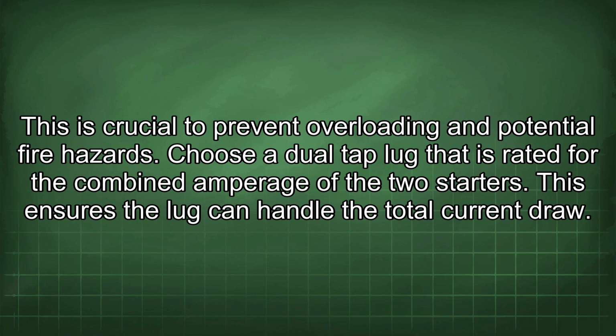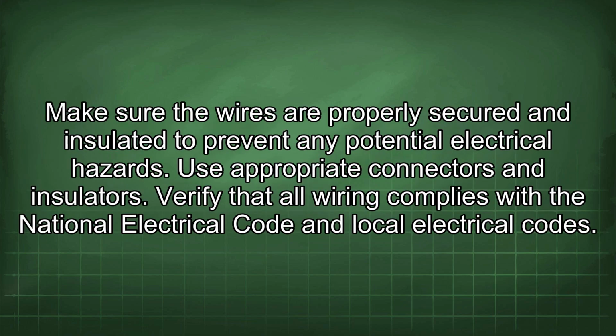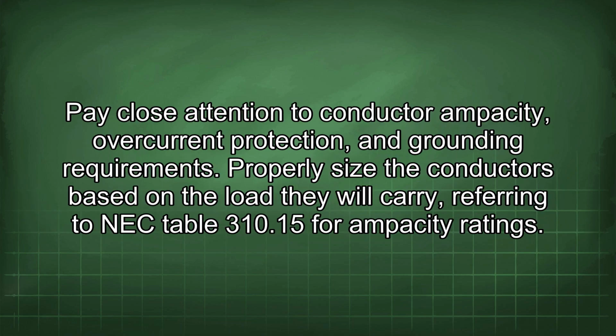Choose a dual tap lug that is rated for the combined amperage of the two starters. This ensures the lug can handle the total current draw. Make sure the wires are properly secured and insulated to prevent any potential electrical hazards. Use appropriate connectors and insulators. Verify that all wiring complies with the National Electrical Code and local electrical codes. Pay close attention to conductor ampacity, overcurrent protection, and grounding requirements. Properly size the conductors based on the load they will carry, referring to NEC Table 310.15 for ampacity ratings.